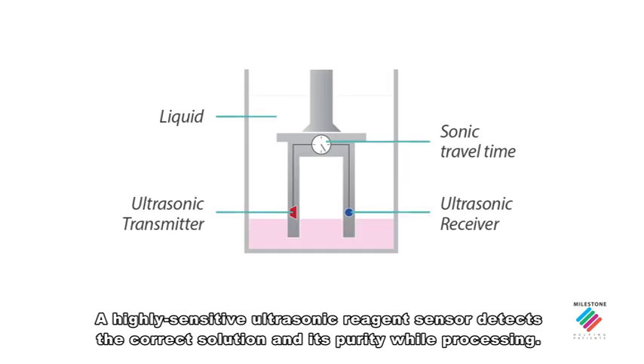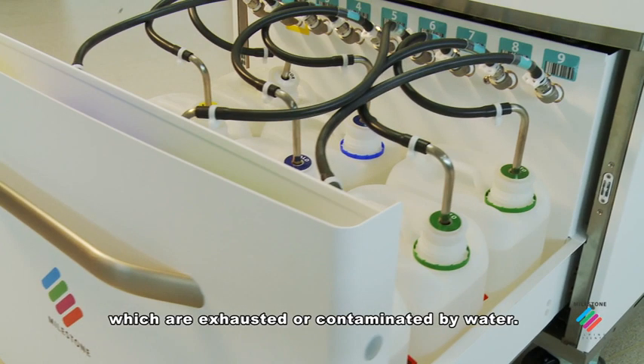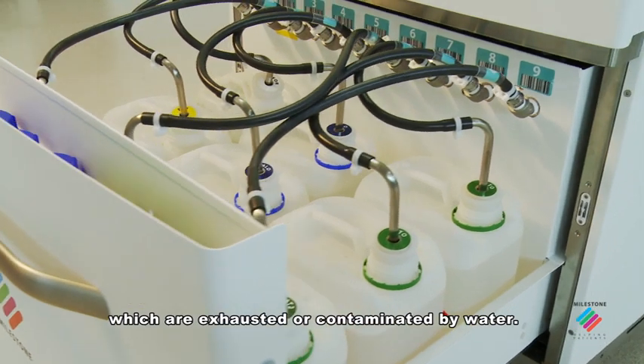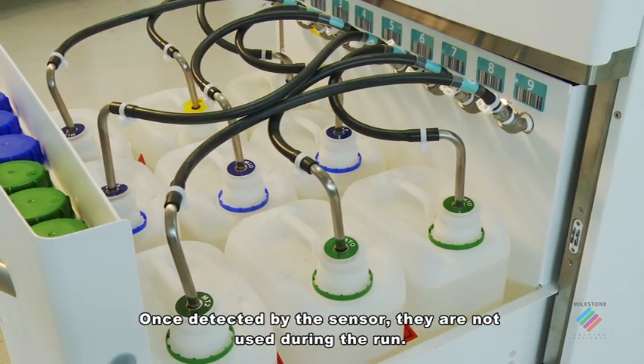A highly sensitive ultrasonic reagent sensor detects the correct solution and its purity while processing. This sensor allows for full specimen safety by detecting any alcohol-based reagents which are exhausted or contaminated by water. Once detected by the sensor, they are not used during the run.